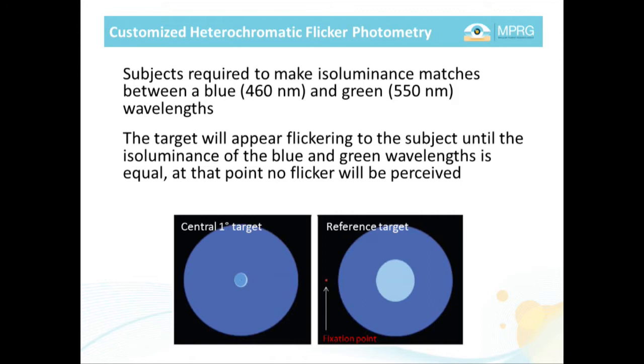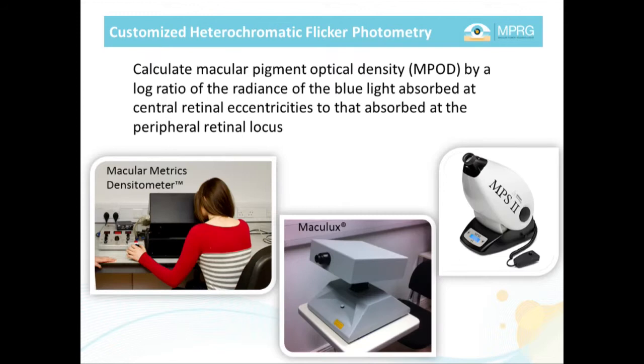The first technique I'll discuss is customized heterochromatic flicker photometry. We use a research model called the Macular Metrics Densitometer, but there are lots of clinical devices on the market, including a few downstairs in the exhibit hall. Subjects are required to make isoluminance matches between a blue and a green wavelength. With our device, the target appears flickering until that isoluminance match has been made, then it appears still. We take that radiance measurement of the blue and calculate the log ratio of blue light absorbed at the macula to a peripheral reference point. There's our research device, a more clinical faster version, and the MPS.